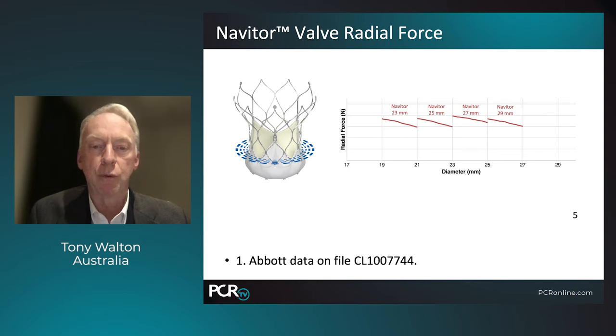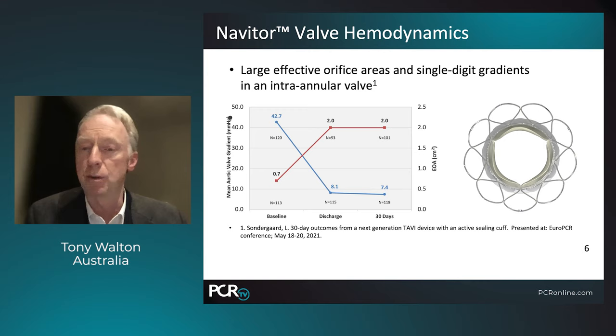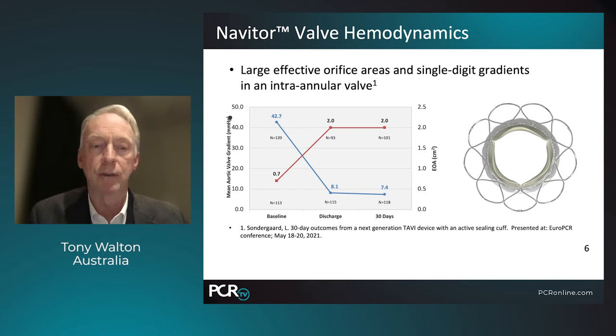Radial force has also changed and improved, and you can see across the 23, 25, 27, and 29 millimeter Navitor valves the radial force is very similar. The greatest radial force comes from the 27 millimeter valve. The valve hemodynamics are excellent, consistent with what we expect from self-expanding valves: large effective orifice areas and single-digit gradients. Mean gradients are between seven and eight millimeters of mercury, comparable to other self-expanding valves and considerably better than balloon expandable devices. Valve area is also excellent at around two centimeters squared across this range.